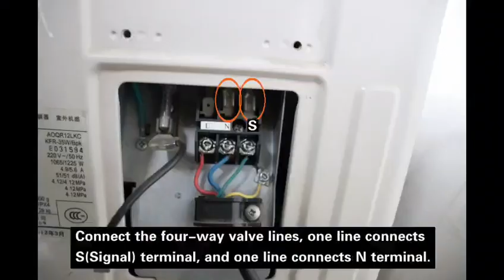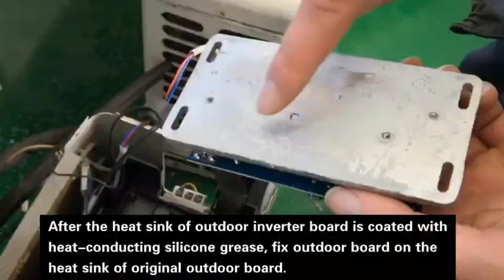Connect exhaust temperature sensor with the compressor exhaust terminal. Connect the four-way valve lines. One line connects S terminal and one line connects N terminal.